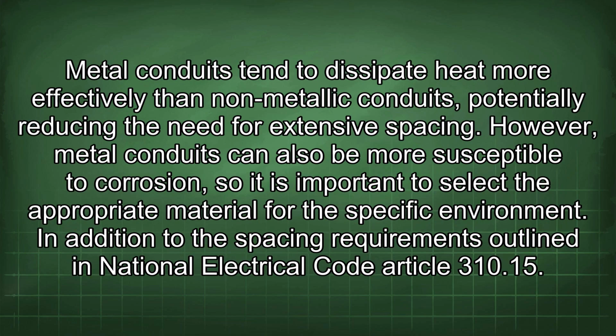Finally, the type of conduit material can also play a role in heat dissipation. Metal conduits tend to dissipate heat more effectively than non-metallic conduits, potentially reducing the need for extensive spacing. However, metal conduits can also be more susceptible to corrosion, so it is important to select the appropriate material for the specific environment.